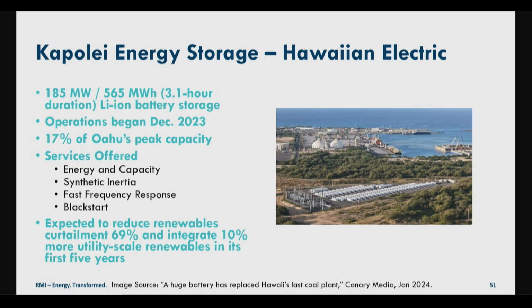Inverters themselves can be set up in a mode called grid forming mode, where they can synthetically provide inertia as a rotating mass might. This is really a software configuration for how these inverters are programmed. There are some case studies, I believe in Australia and Hawaii, for this synthetic inertia feature. It's one of the advanced features, not something I went into detail on in the presentation, but is maybe increasingly important for grids with high amounts of inverter-based resources.